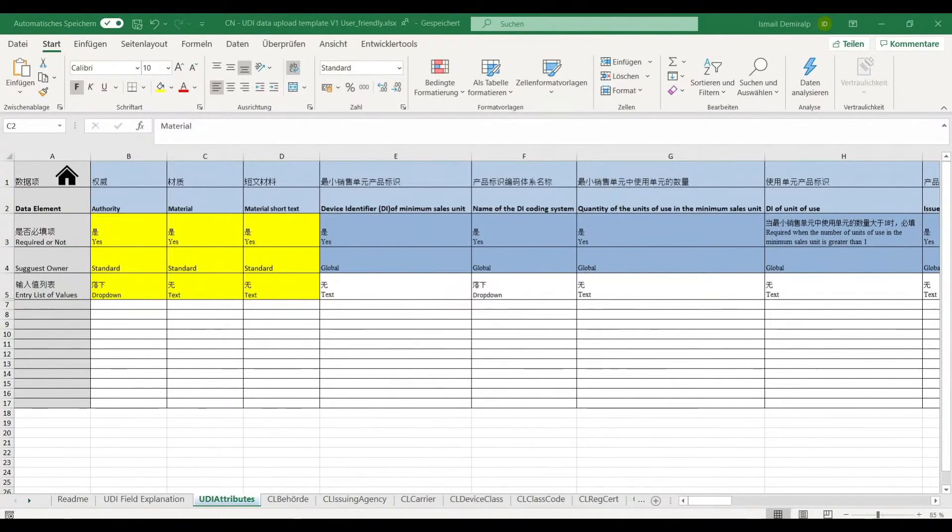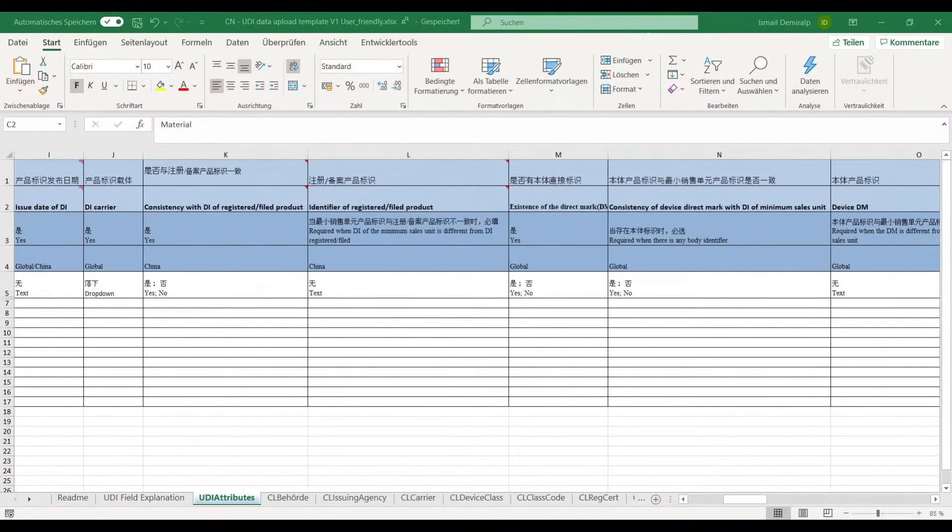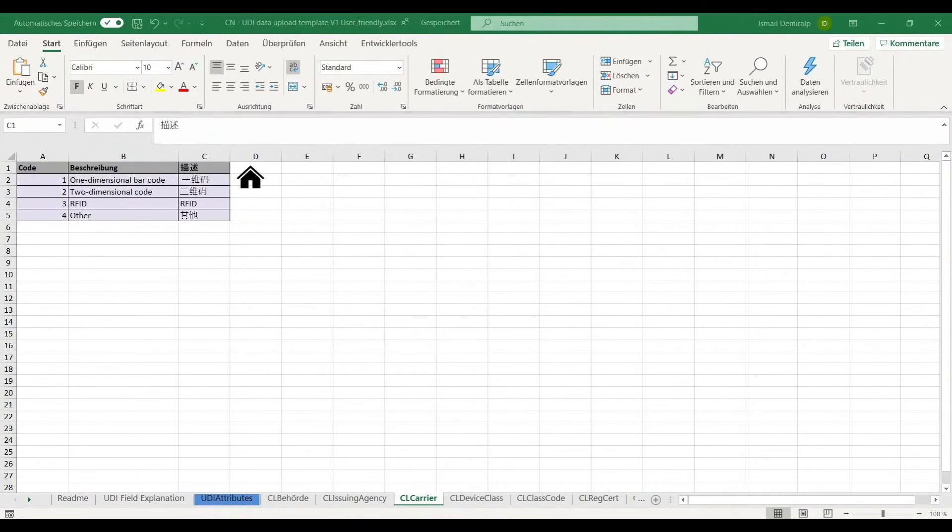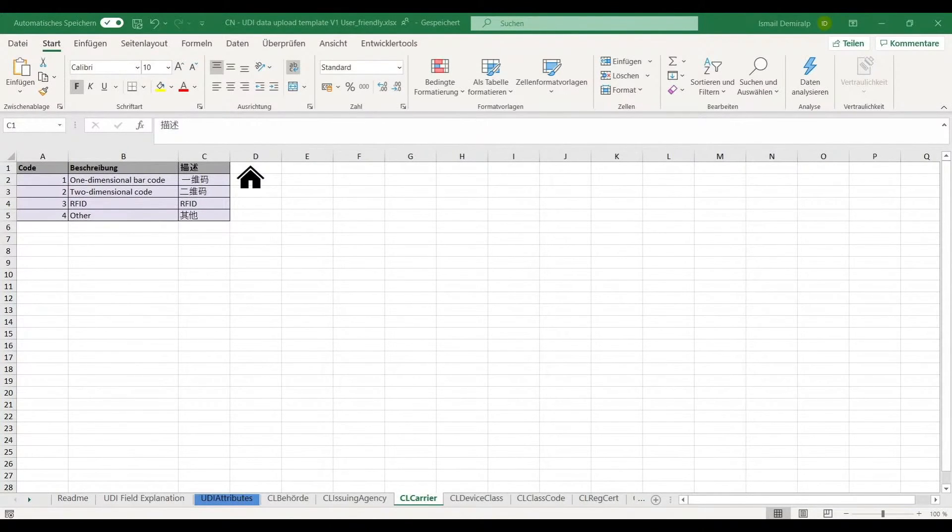On the third sheet, UDI attributes, you can input your UDI data line by line. These data will be later submitted to the NMPA. The other worksheets are used to provide code lists in drop-down to help you filling out the form. For instance, on the sheet CL-carrier, a code list for carriers.